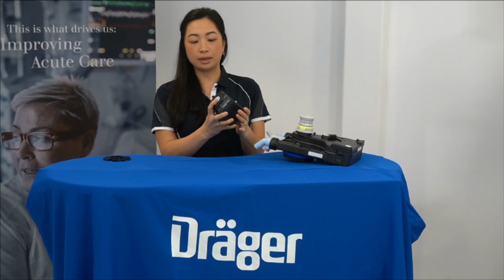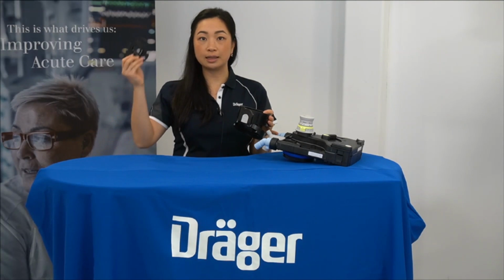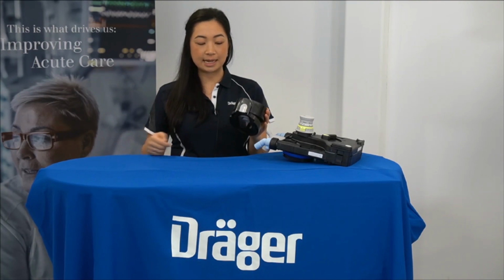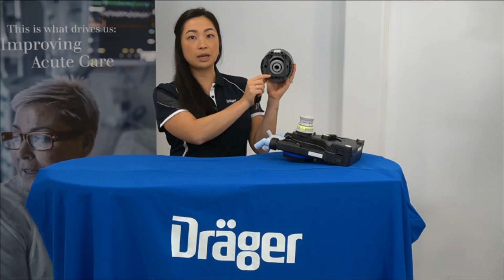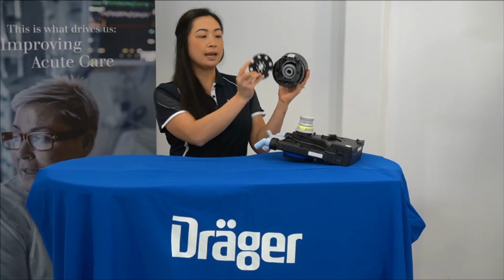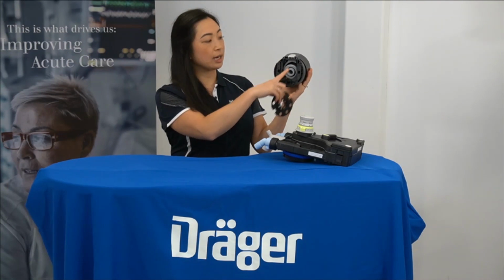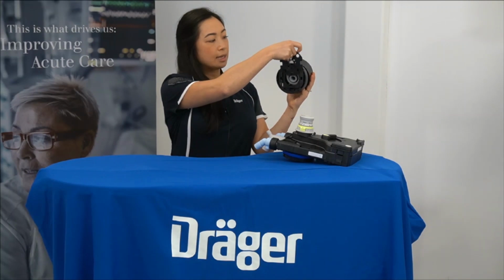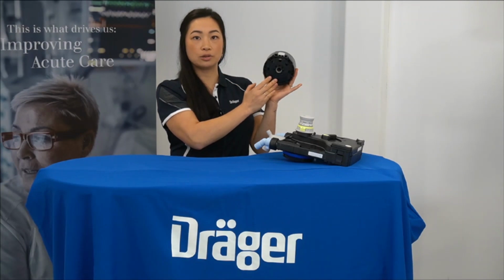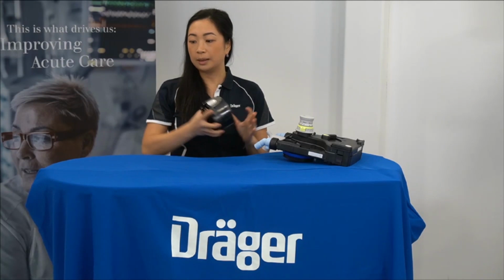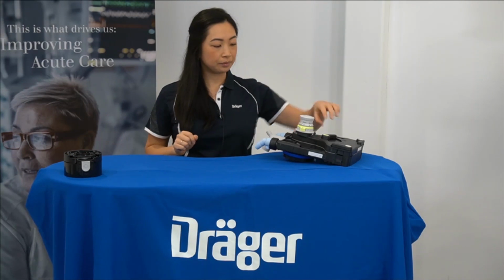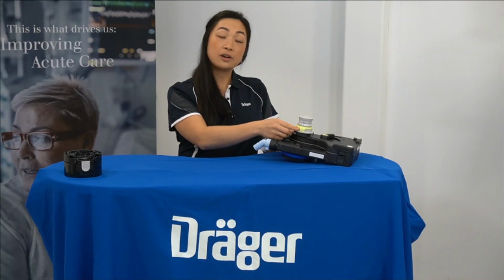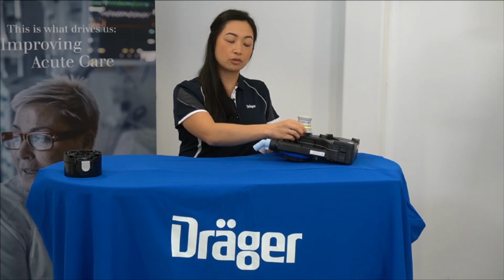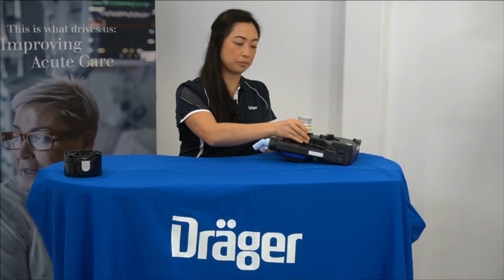At this point, it is good practice to insert the cleaning plate in. This is done by pressing the grey button to open up the click adapter, lining up the straight edges with the straight edges here, and sliding the plate in and closing the click adapter. Then place that to the side. Then the APL valve can be removed by unscrewing the bottom grey component.